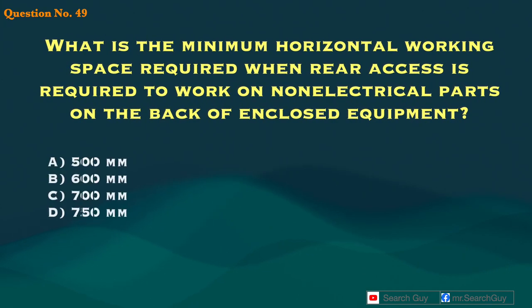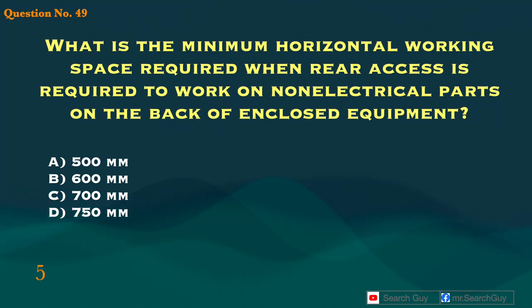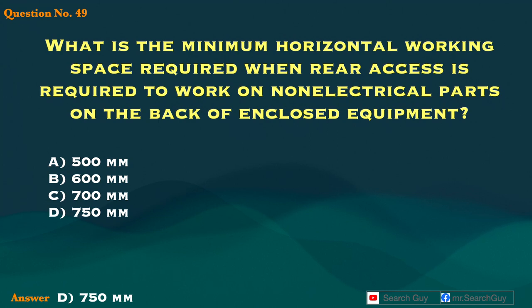Question 49. What is the minimum horizontal working space required when rear access is required to work on non-electrical parts on the back of enclosed equipment? A. 500 millimeters. B. 600 millimeters. C. 700 millimeters. D. 750 millimeters. Answer: D. 750 millimeters.